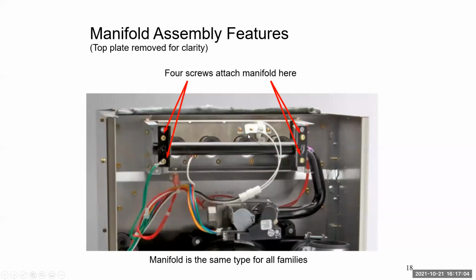Manifold assembly, it's pretty much the same manifold assembly across the board. One big thing here is if you have that thing apart, when you get your ground back in, make sure that screw is tight and not stripped out, or you will have problems. That ground has to be tight. And with that said, if you're going out on reverse polarity issues or trip outs, things like that, just hit that screw real quick and make sure it's tight before you do anything further, so you don't have that problem.